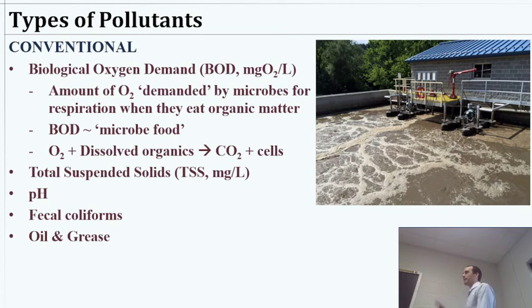It's typically this soil brown color, and if you've got a wastewater treatment plant operating well, and you've got plenty of air, you don't have anaerobic processes when you wanted aerobic, it actually shouldn't smell too bad, technically. It should smell a little musty, maybe a little like dirt or forest decay matter, not too unpleasant. It's really when you get anaerobic processes that it becomes more unpleasant.